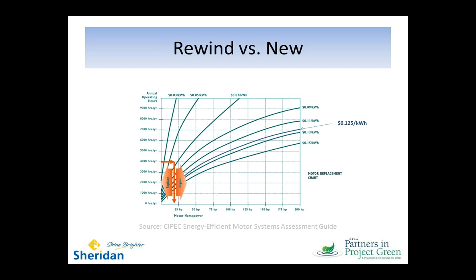If you've got a motor that's 100 horsepower or bigger and operates less than 4,000 hours, so essentially it's this quadrant here in the graph, that's one that you should try to rewind as long as your core iron is still within specification. If you've got a motor larger than 50 horsepower, you could rewind it really about 3 times, after which point you really should be thinking about replacing that motor. And the motors that fall between that repair-replace breakpoint should be replaced with the PEM and not rewound.